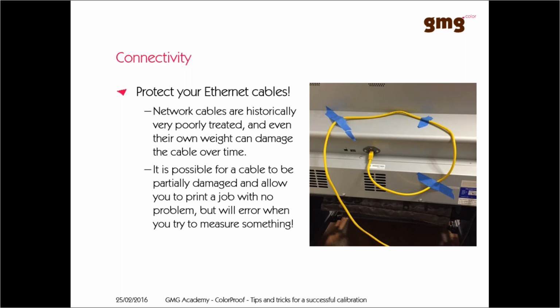The very mean thing is, when you have a cable which is just partially damaged, you may still be able to print a job, but when the measurement information should come back to the software, you get an error. And then you have to investigate a long time until you find out it's the broken cable. So here you see a picture from my colleagues from the USA. This is how they do it. They loosely just stick the Ethernet cable to the printer to prevent the cable from damaging itself, for instance.